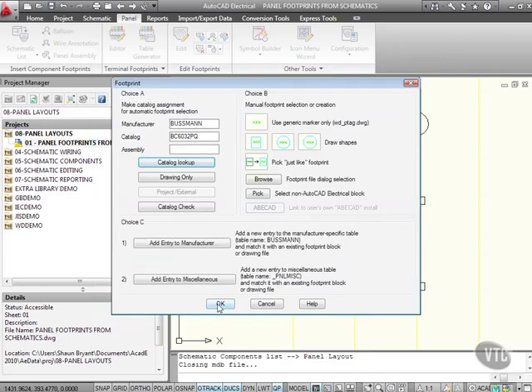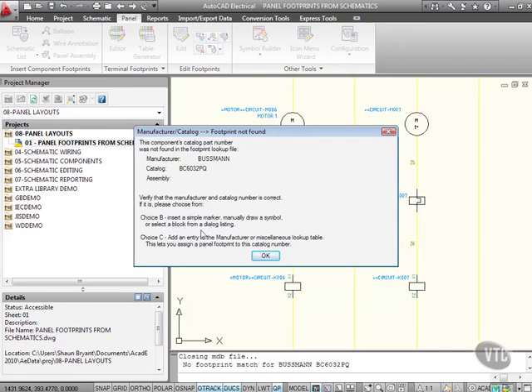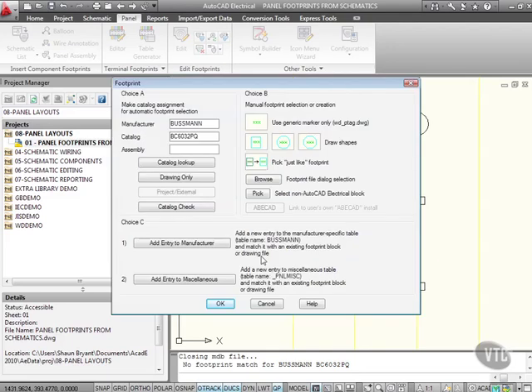This component's catalog part number was not found in the footprint lookup file. I can either insert a simple marker, manually draw a symbol, select a block from a dialogue listing, or add an entry to the manufacturer or miscellaneous lookup table to assign a panel footprint to that catalog number.